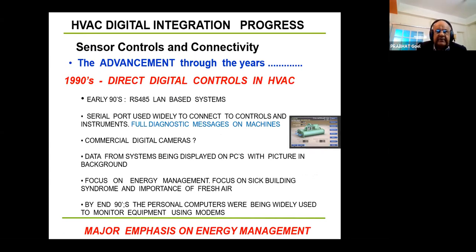I had the unique privilege around that time to set up an RS-485 LAN using thermostats in different rooms of an accommodation complex, with a damper connected to each thermostat. Air was supplied by a central air handling unit on top of the roof, and each room had its own VAV damper, with the LAN finally connected to the serial port.